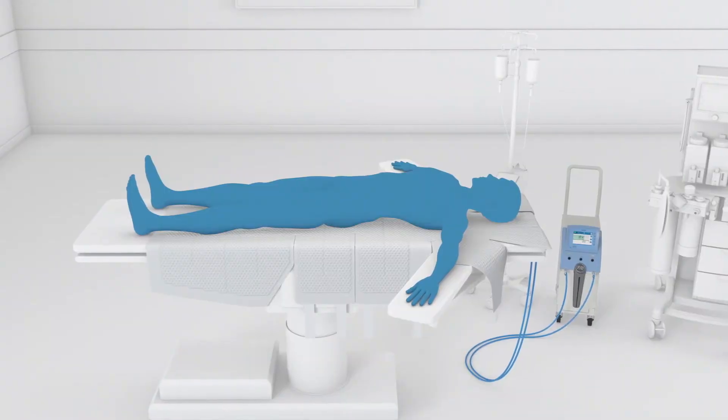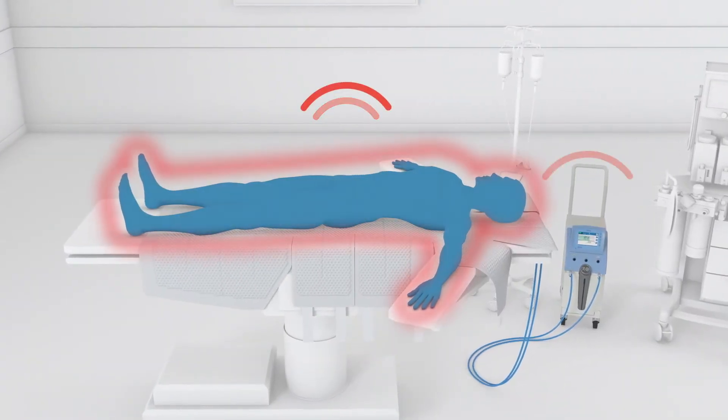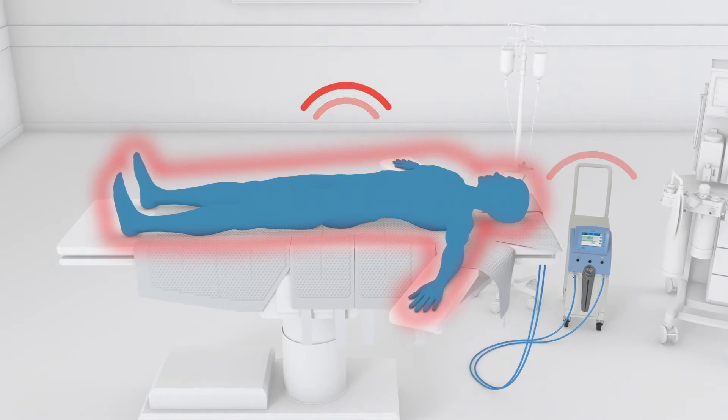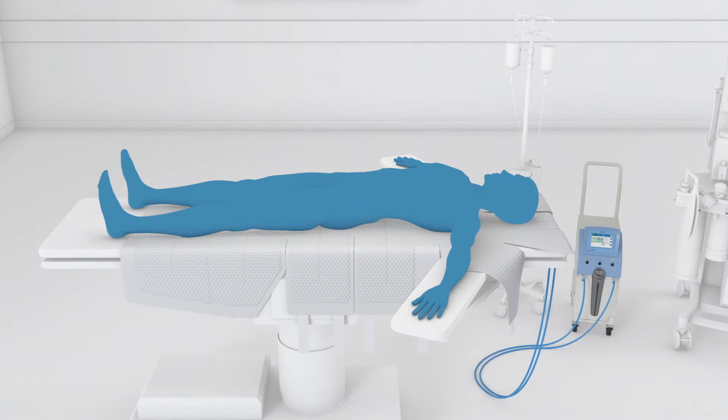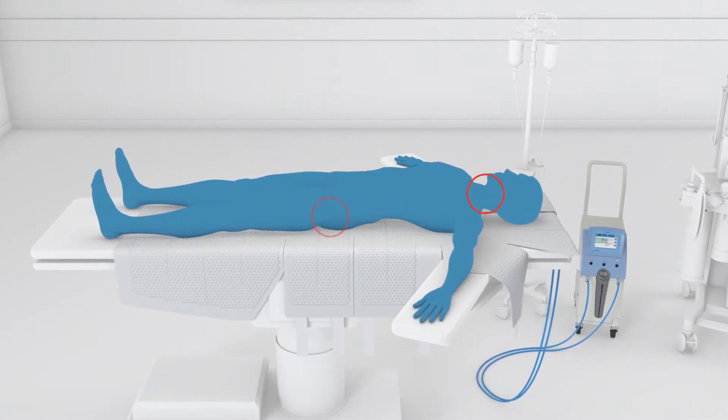In the default normothermia mode, Allon relies on constant patient temperature feedback from both core and skin probes to maintain normothermia. Core temperature can be measured by esophageal or rectal temperature.